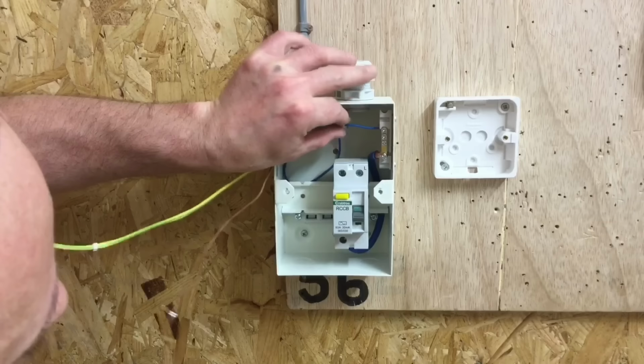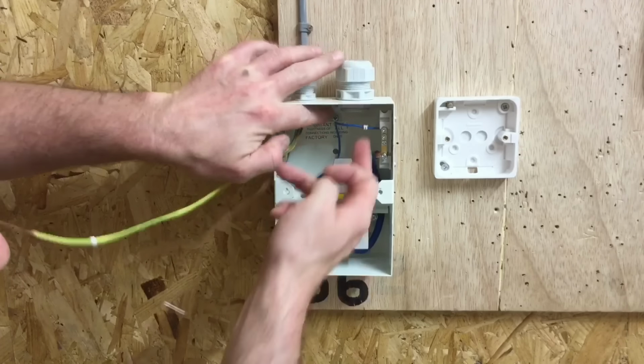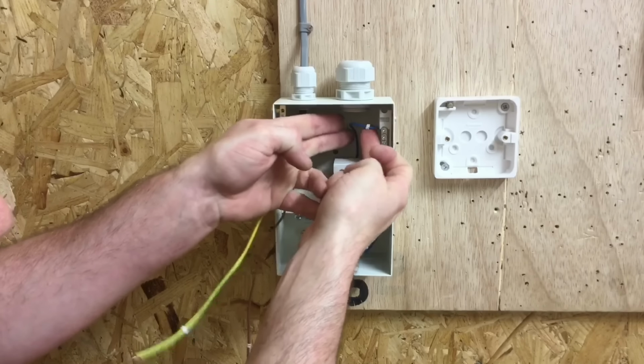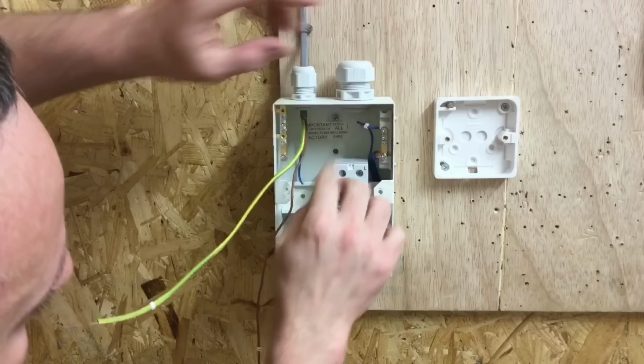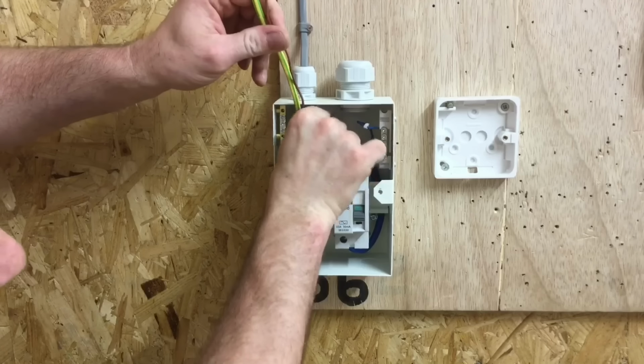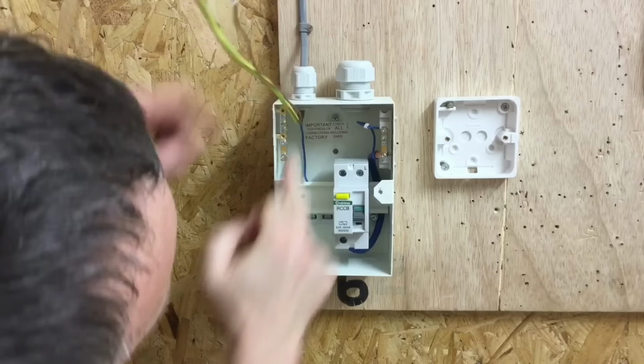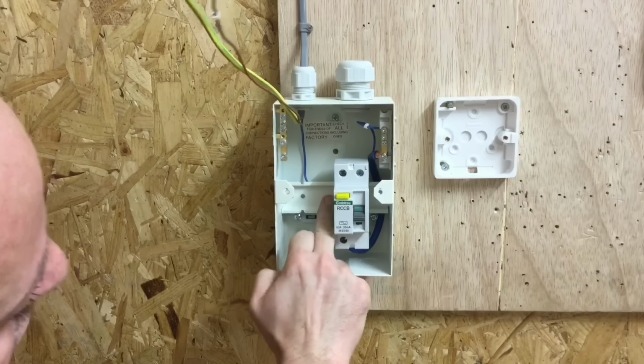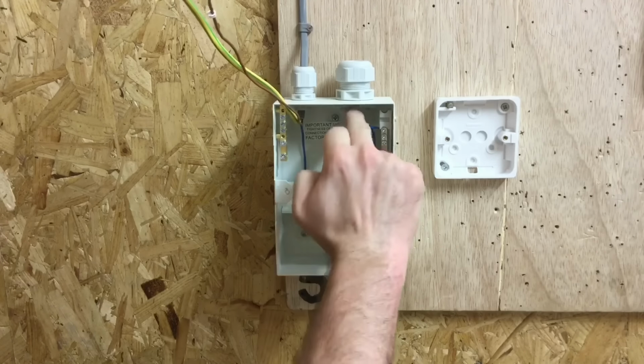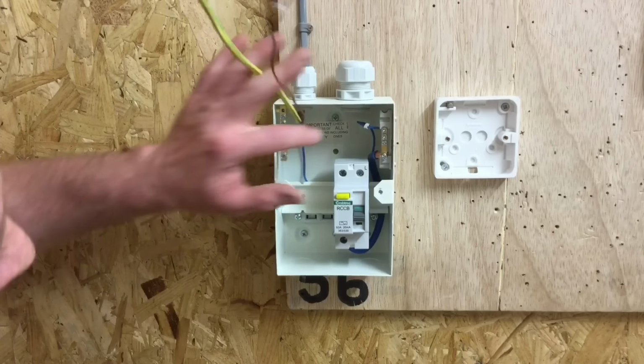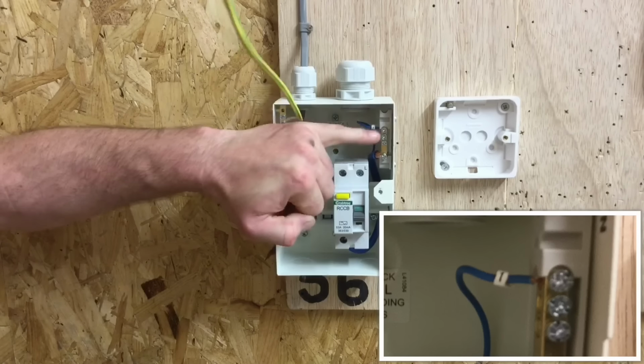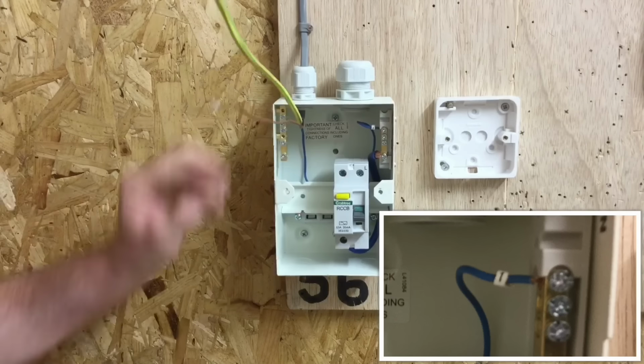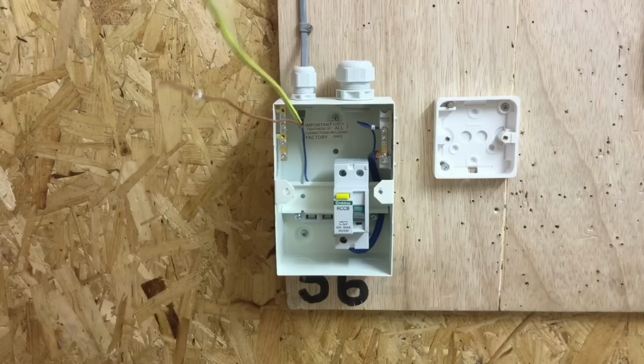Now I can dress it. Need to make sure that I can see the number 1. I want to make a gentle smooth bend in the distribution board, remembering my tails will be coming in from the top at some point. So I've come down straight, I've gone on top of the bus bar at the back here, came up and got a nice smooth bend. I make sure I can see the number 1 and I've used the top termination for the neutral. I'm going to go on and do the circuit protective conductor next.